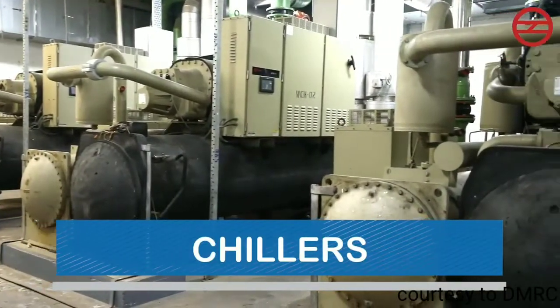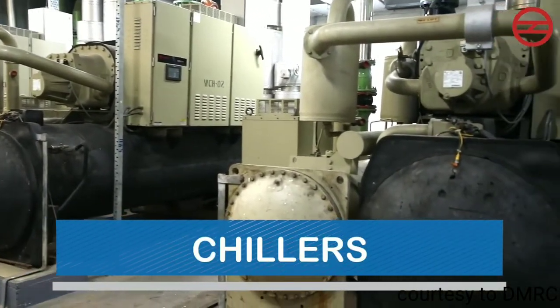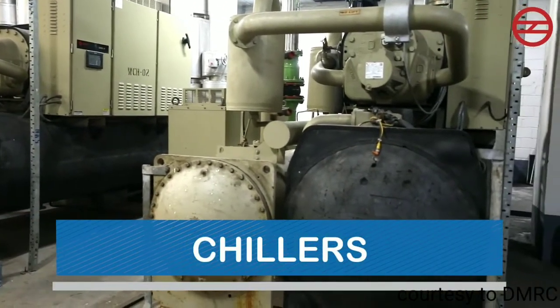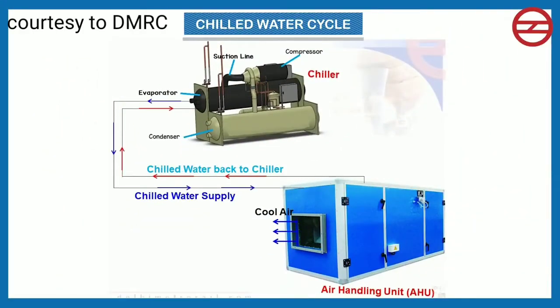Chillers are the most important component of air conditioning arrangement. They are responsible for operating three different cyclical processes. First is the chilled water cycle. In this cycle, chilled water is continuously supplied by chiller's evaporator to the AHUs. This chilled water absorbs the heat from the air and returns to the chiller.